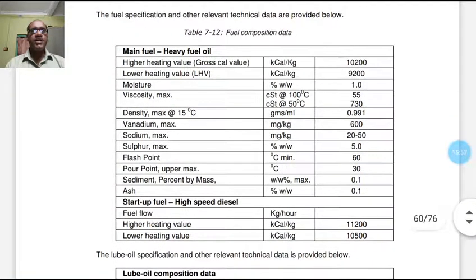Fuel composition data: heavy fuel oil, where the higher calorific value, gross calorific value and lower heating value are provided, that is 10,200 and 9,200 respectively, kilocalorie per kg. It is measured. Moisture 1%. Viscosity measured in centistoke at 100 degree centigrade and 50 degree centigrade respectively are 55 and 730. Density at 15 degree centigrade is 0.991, and some other impurities, vanadium, sodium, sulfur, are there.